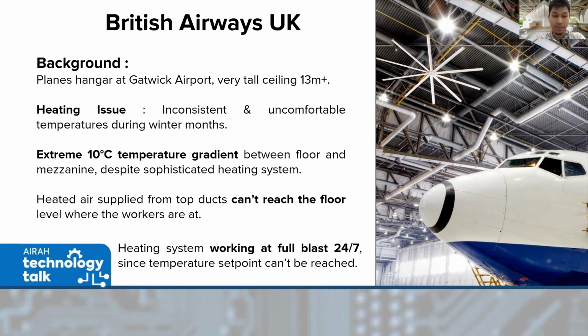They had an extreme 10 degree temperature gradient between floor and mezzanine, despite spending a lot of money on a sophisticated heating system. The heating had to run full blast 24/7 because the temperature sensor was at occupant level and that set point could never be reached, so the electricity bill was astronomical.